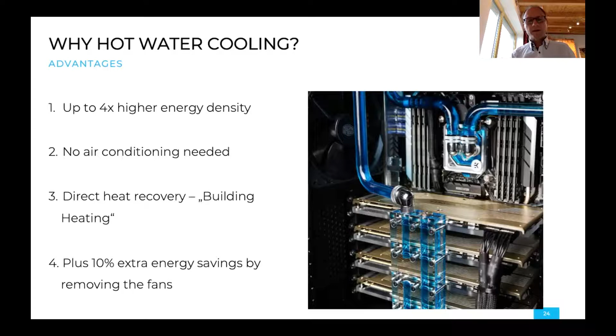And you can do direct heat recovery. Once you have the heat in the water, it's much easier to transport it and bring it into the building where it can be used. And we don't need any fans anymore, so that gives us a 10% extra energy saving by removing those fans.